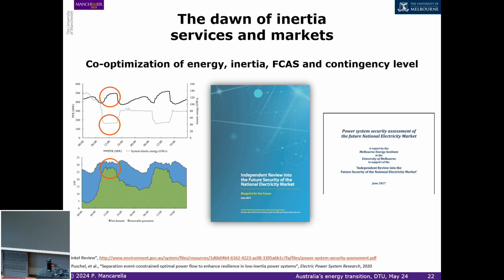Unless you actively manage the largest contingency - which can be a larger generator, or in the case of a separation event, the flows across interconnectors - either you cannot save the grid, or it becomes too expensive, requiring too many reserves.